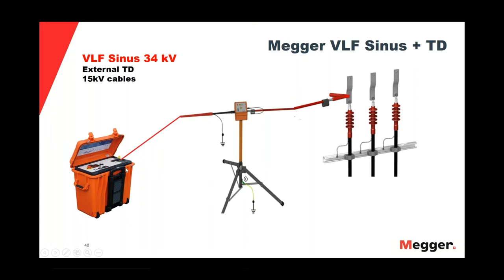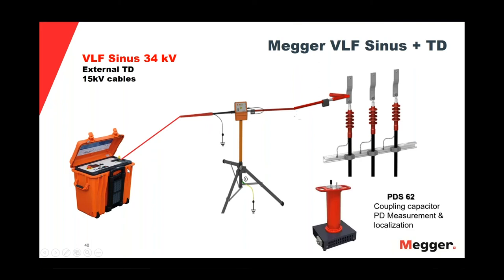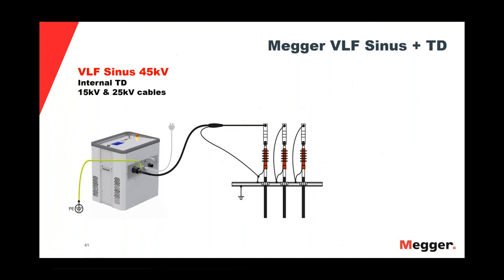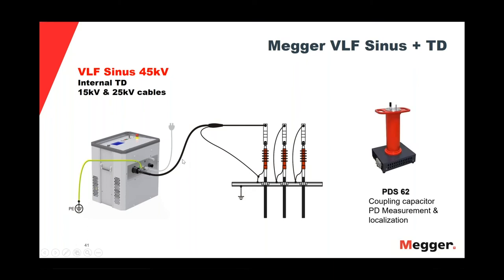Before we go to the next one, of course, we have the option to buy the PDS62, that is a coupling capacitor, to measure and localize the partial discharge in the cable. So with this unit, we can do the three most important tests we do in cables: VLF, tan delta, and partial discharge. The next unit we have is the VLF Sinus 45 that we use to do the VLF test in 15 kV and 25 kV cables. This unit has an internal tan delta, for that reason the connection is very easy. And of course, also we have the option of the coupling capacitor to measure and localize the partial discharge.